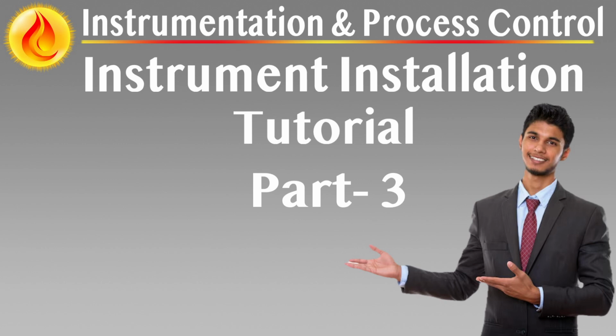External purging, active flow assurance for clean, unobstructed signal transmission. Purpose and application, clearing the path for accurate measurement. External purging is employed when passive strategies like sloping impulse lines or diaphragm seals are insufficient to prevent plugging, condensation, or vaporization in the measurement path.